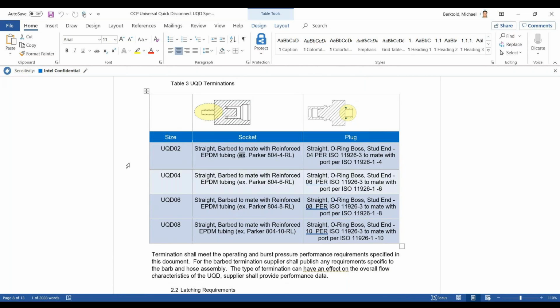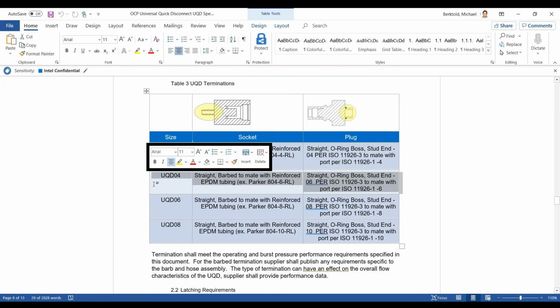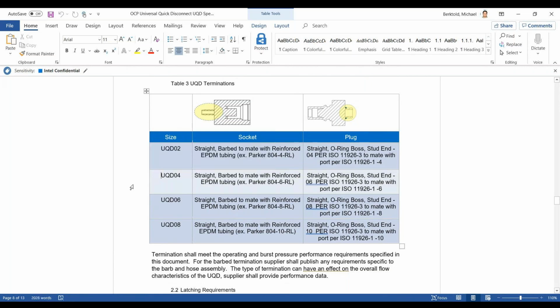So was it based off of a DIN standard, or did you guys come together and agree on a barb geometry? There's no, as you know, there's no real standard for that barb geometry. Yep. So when we received these based on the specification, there were differences definitely in the terminations. However, all of the terminations and the connections held up in our validation testing, and so it would be expected that for whatever tubing is being specified by the end user, they would work with the suppliers to make sure that would work. Got it. Okay. Yeah, it's not a fun area. That's why, as you know, it gets complicated. Yeah. Be cool if someone came out with an ISO standard or something for that barb geometry.